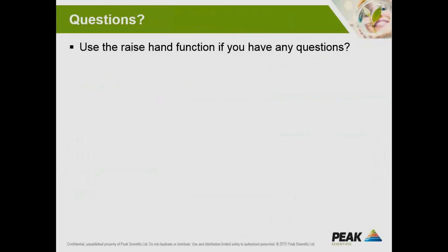I guess, Mr. Dixit. Yeah, I'll just take the next question from Mr. Narasimha Prasad, who says, how many GCs can be connected to one generator, and I guess he's speaking about the zero air. I've unmuted Mr. Prasad.